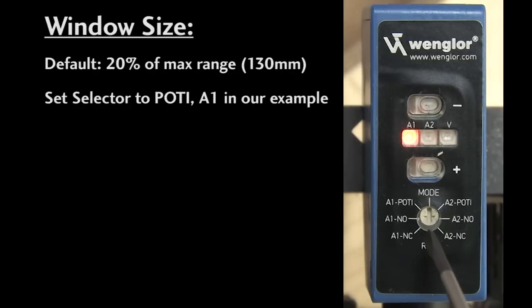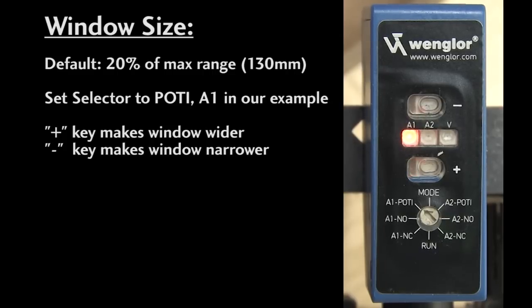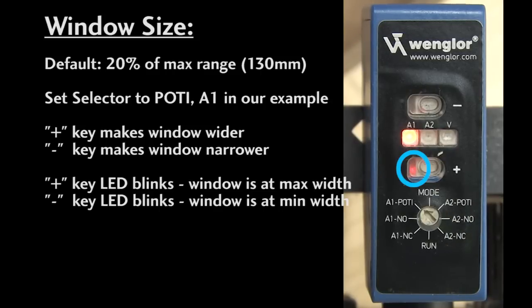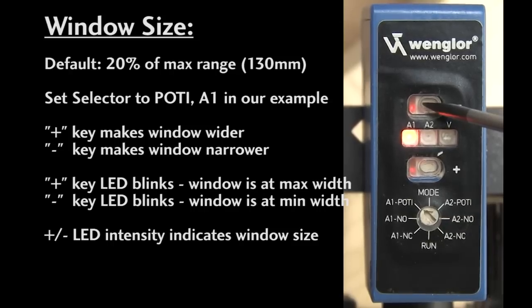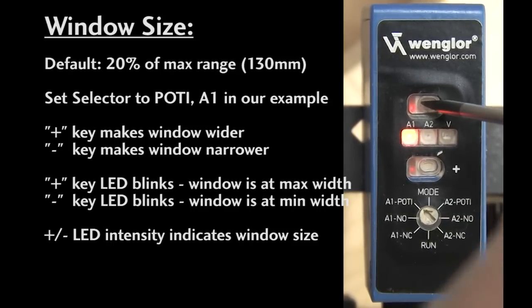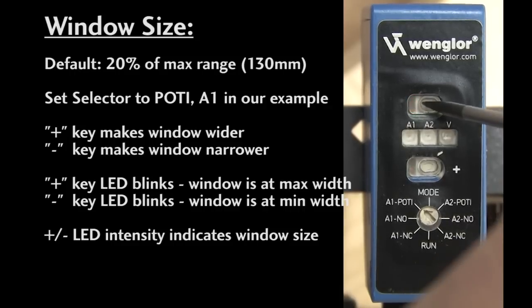Sure. Set the selector to the POTI for that output – A1 in our case. The plus key makes the window wider and the minus key makes it narrower. If either key blinks like this, then you've hit the upper or lower limit of the allowed window width. It's a little subtle, but if you look closely you can actually gauge where you are by watching the LEDs.